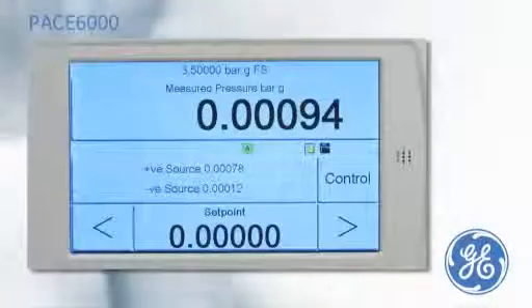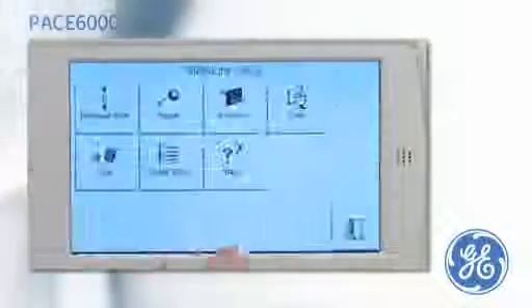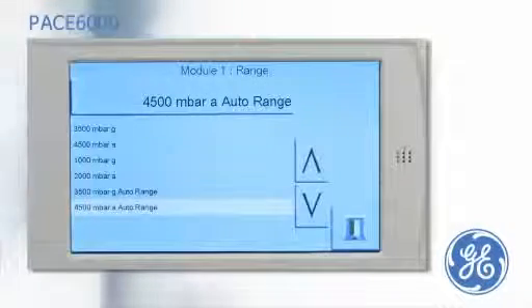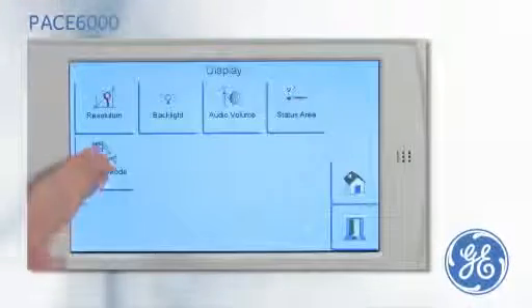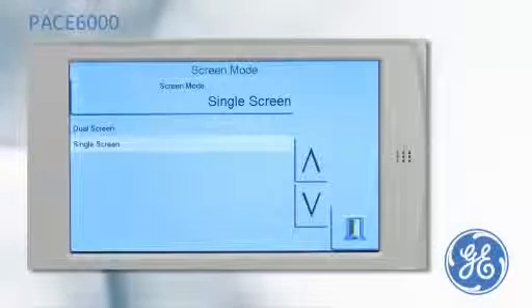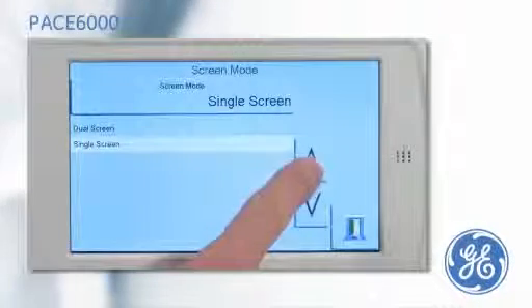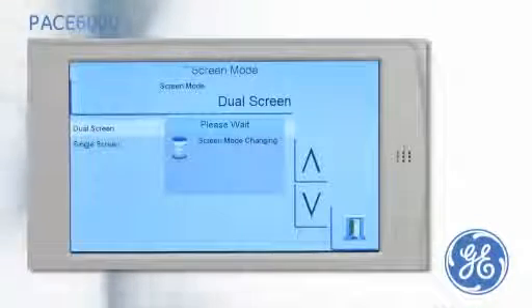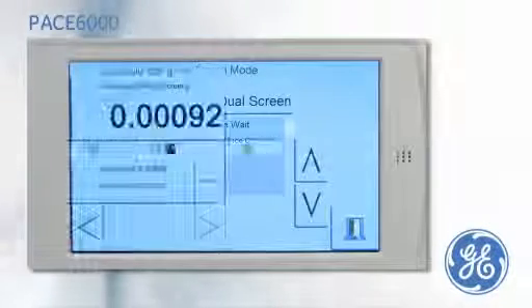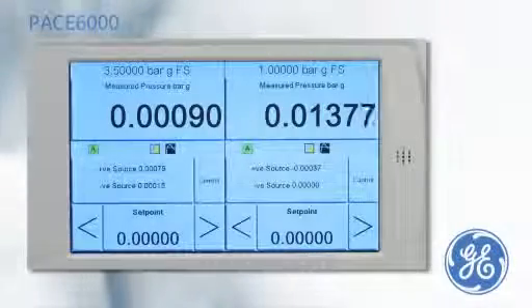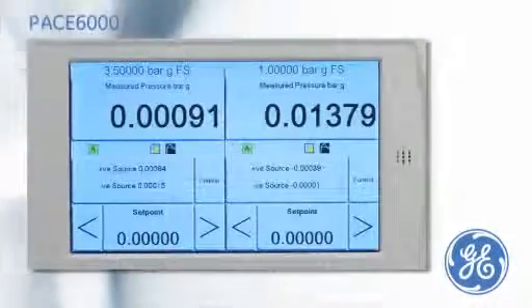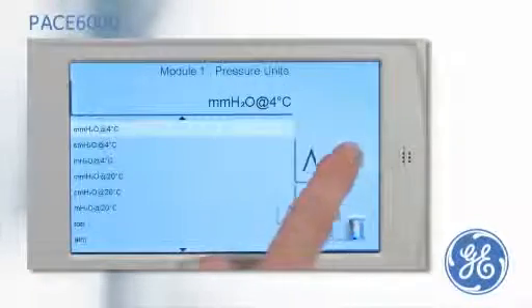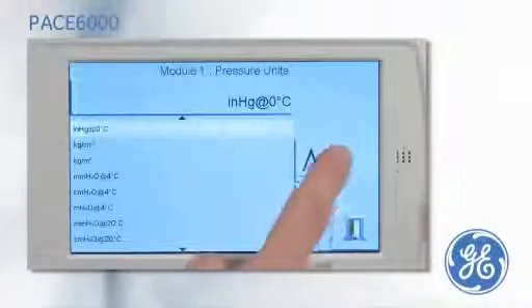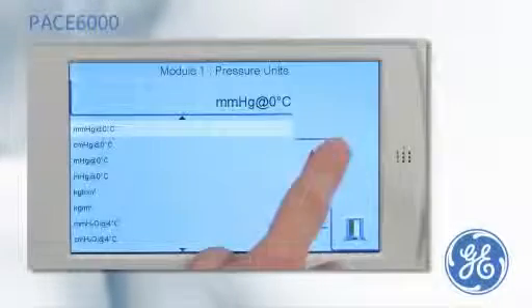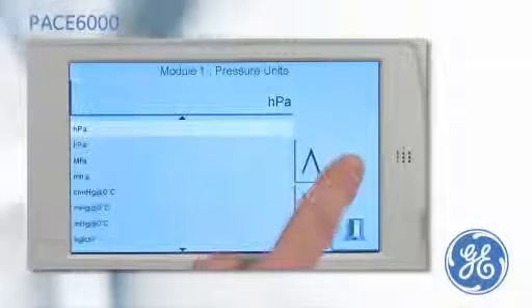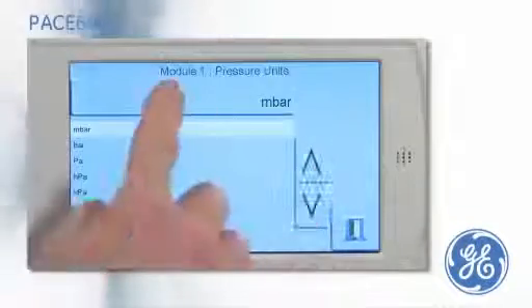Using the intuitive menu, the pressure range or auto range can be selected from the choice of up to two installed control modules. If two control modules are installed, the user can also determine if the PACE6000 is to be used in a single channel mode or in a dual channel mode. The dual channel mode will enable an operator to control two pressure outputs simultaneously. Once the range and either single or dual channel mode have been selected, the operator should select the pressure units to be displayed in line with the units of the device under test.